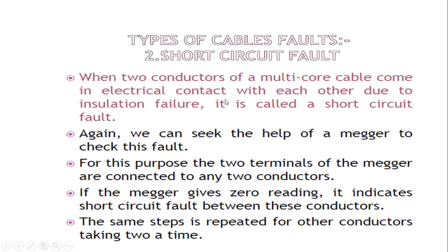If the insulation between the two conductors fails, then the two conductors come in electrical contact. In that case, short circuit faults are obtained. Therefore, again we can seek the help of a Megger to check this fault. By using the Megger, we identify the short circuit faults that are obtained in the conductor.